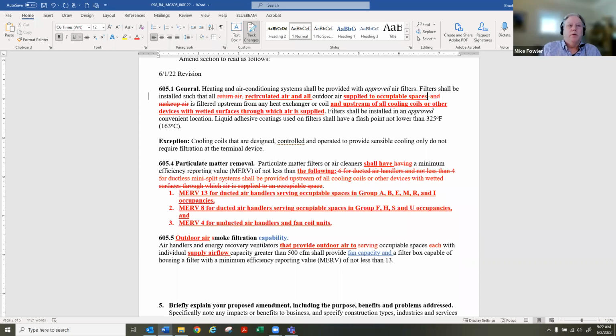Your summary, Mike, was exactly what I think is being proposed here. And yes, say a DOAS system, since it does not have specific heat or cooling within it, would fall into 605.5 outdoor air. And then if it was above 500 CFM, 605.5 would apply to that type of residential system. If that answers it. Okay, thank you.